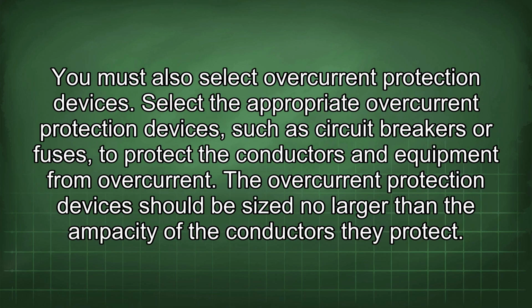You must also select overcurrent protection devices. Select the appropriate overcurrent protection devices, such as circuit breakers or fuses, to protect the conductors and equipment from overcurrent. The overcurrent protection devices should be sized no larger than the ampacity of the conductors they protect.